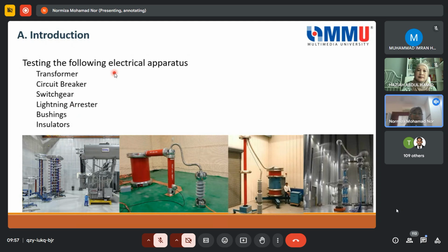Okay, so these are the testing. What is the purpose? Of course, we want to measure the voltage, basically voltage and current, when we do the testing on this equipment. These are just some of the equipment, such as transformer, circuit breaker is not here, but you can see lightning arrestor and bushing, as well as the insulator here. And I'm sure that you have covered this in your testing, because like at MMU, we have measurement and testing. So the testing, we have learned about how to do the setup and so on.